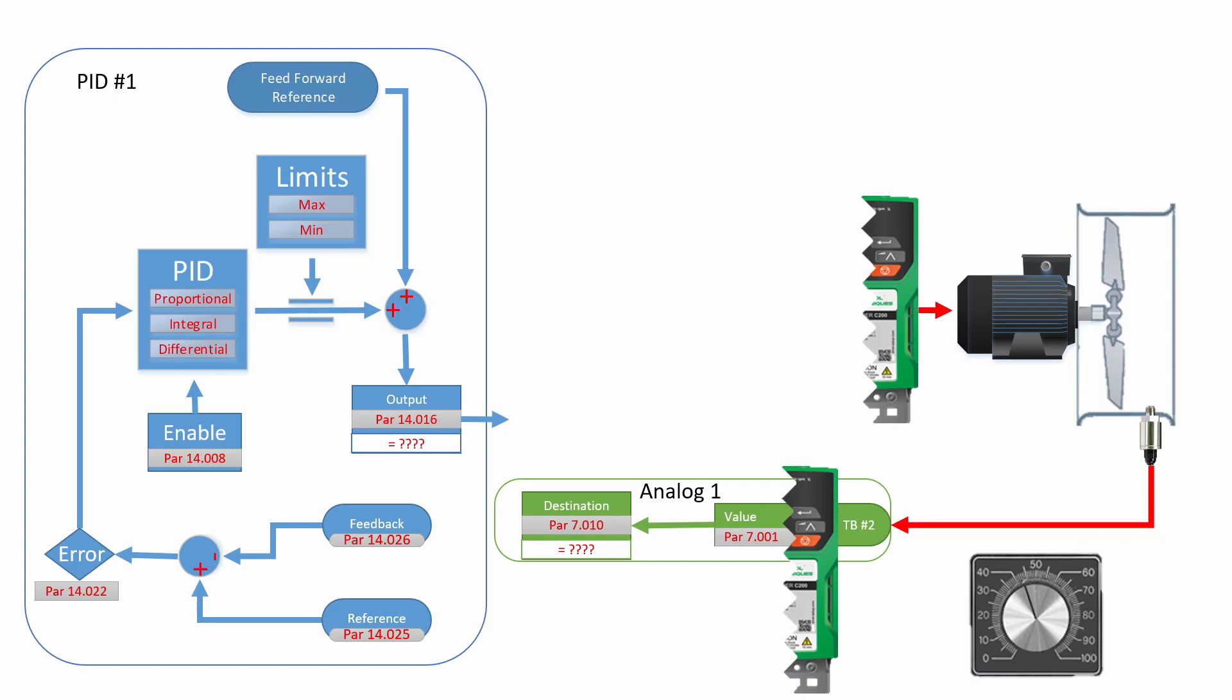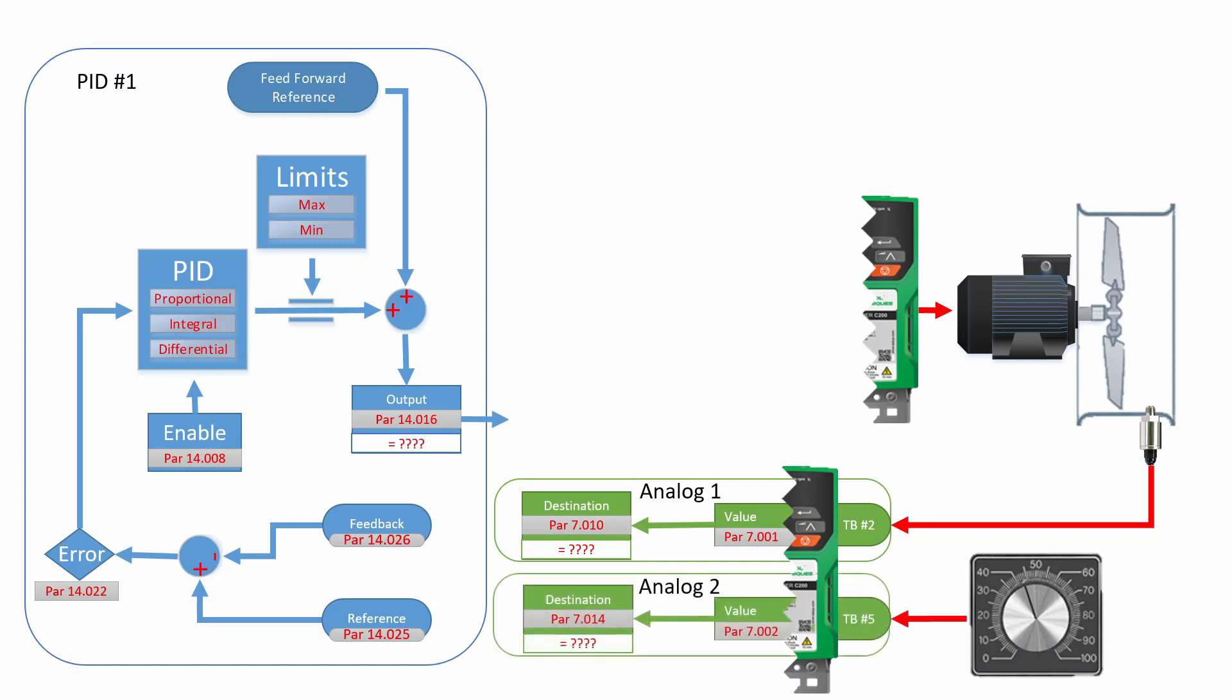The analog value will then be sent to whatever destination is in parameter 7.010. To wire up the potentiometer, we're going to wire it to terminal number 5. This is analog number 2. Its value will show up in parameter 7.002, also as a percentage, and it will send whatever's in 7.002 to the destination found in 7.014.